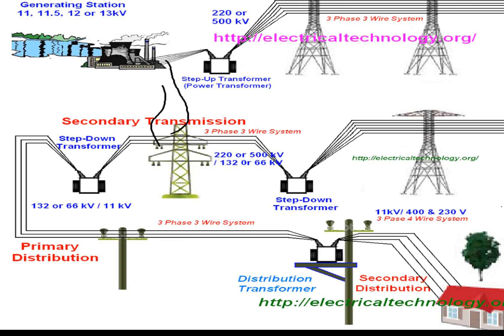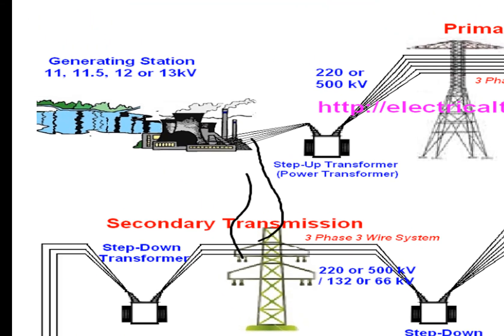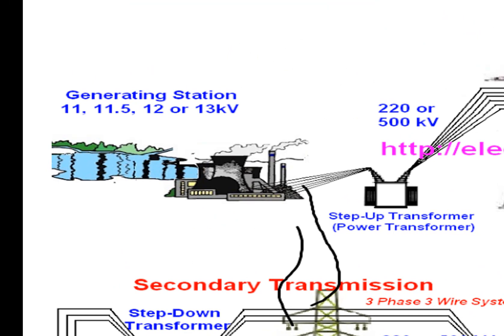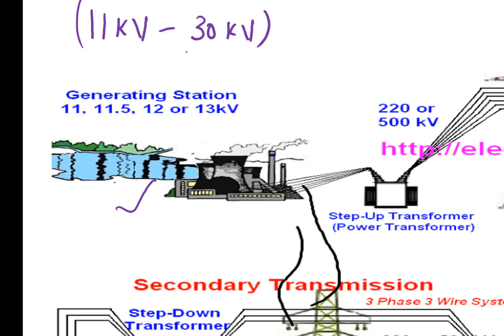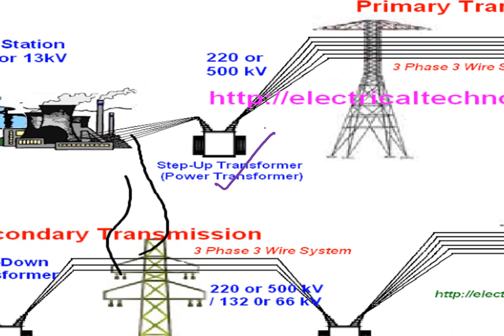To understand vaguely how the power system works: electrical energy is generated at generating stations. The generation voltage is usually from 11 kV to 30 kV. After generation, there is a step-up transformer which steps up the voltage from that lower voltage to a higher voltage, usually in the range of 200 to 500 kV.